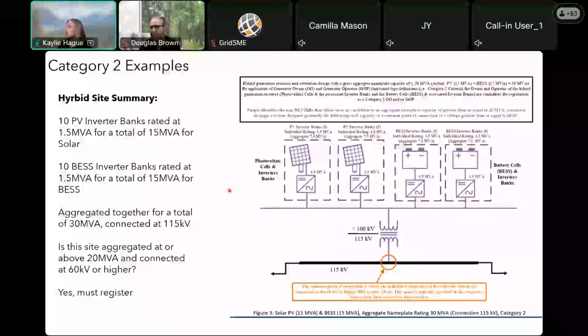Okay, let's take a look at a hybrid site here. On the left, we've got 10 PV inverter banks individually rated at 1.5 MVA, for a total of 15 MVA for the solar side. For the battery side, we've got the same setup, it's just battery. So 10 BESS inverter banks individually rated at 1.5 MVA for a total of 15 MVA for the battery. But they come together and have an aggregate of 30 MVA, and they're connected to the grid on the high side at 115 kV.